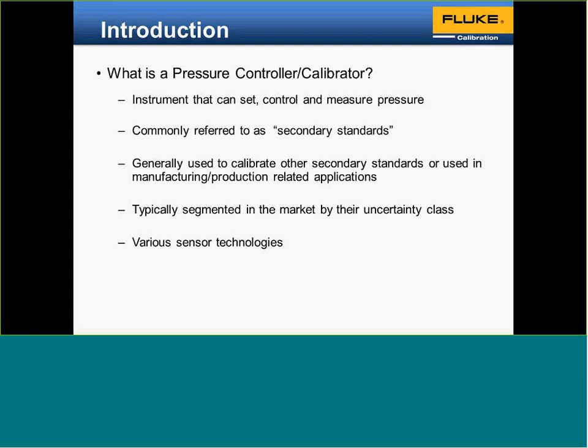So we're talking about an instrument that can set, control, and measure pressure, commonly referred to as secondary or transfer standards in the industry. Pressure calibrators are generally used to calibrate other secondary standards or, in manufacturing production environments, to calibrate items which are at a lower accuracy. Pressure controllers are segmented in the market by their uncertainty class. Different uncertainty classes determine their price, and they utilize various sensor technologies.